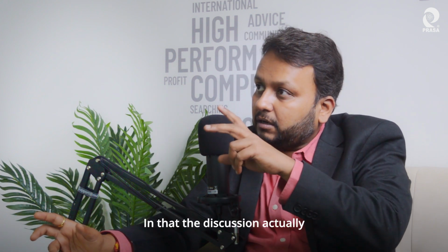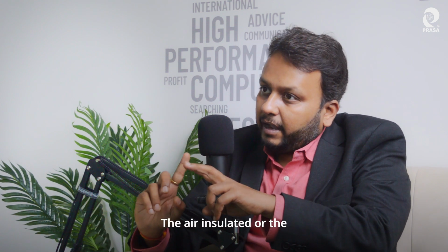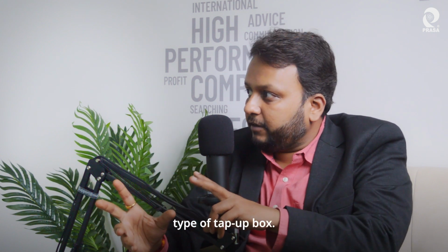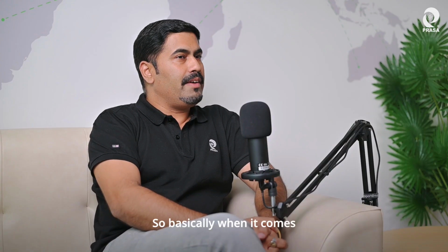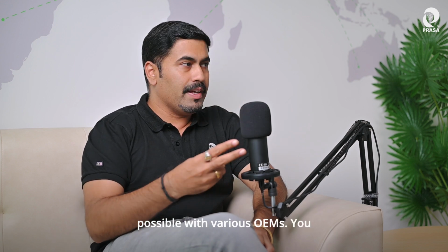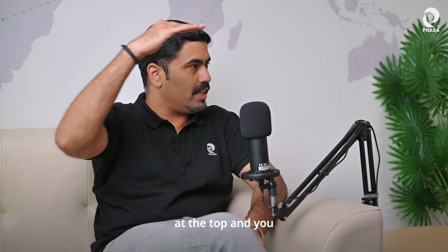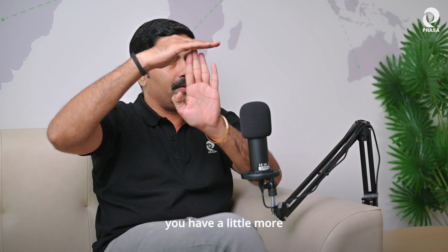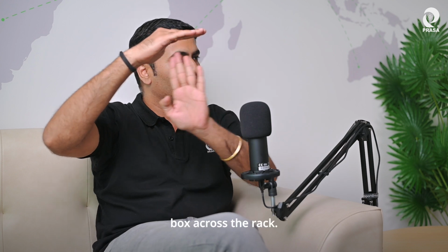In that, the discussion actually went into two directions, and I want some input from your side on that. The air insulated or the sandwich had a different type of tap-off box, and the track had a different type of tap-off box. What is their contribution in terms of height saving? So basically, when it comes to a trackway, there are two options possible with various OEMs. You either can mount the tap-off box at the bottom of the track. So the track is running at the top, and you can mount the tap-off box like this, so that you have a little more space above the rack that is required. But then you get the flexibility, you can move those tap-off boxes across the rack.